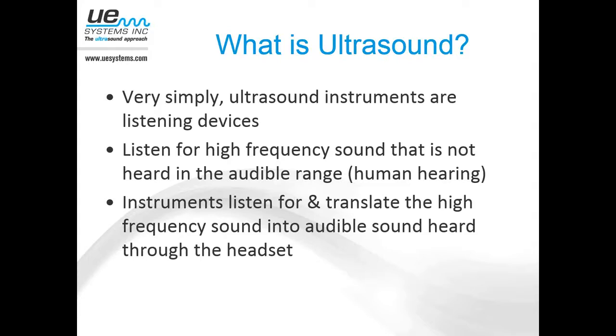Essentially the instruments take that high frequency sound and translate it into something audible we can hear through a headset, but also translate those high frequency sounds into a dB that we can measure. That dB measurement is used to evaluate things like bearing condition over time where we trend it, or the dBs can also be used to put a cost to a specific leak. So it's nice to not only hear the sounds when you're out troubleshooting or trending, but actually put a number to it and assign a value that's trendable and trackable.